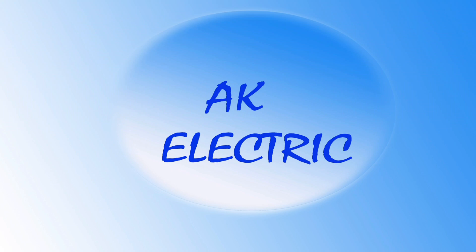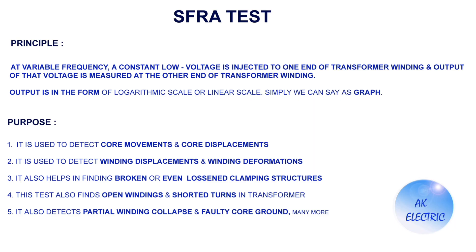Hi friends, welcome to AK Electric YouTube channel. In this video we will see the SFRA test. First we will see the principle of the test. At variable frequency, a low constant voltage is injected to one end of a transformer winding, and the output of that voltage is measured at the other end of the transformer winding. Output is in the form of a logarithmic scale or linear scale — simply, a graph.